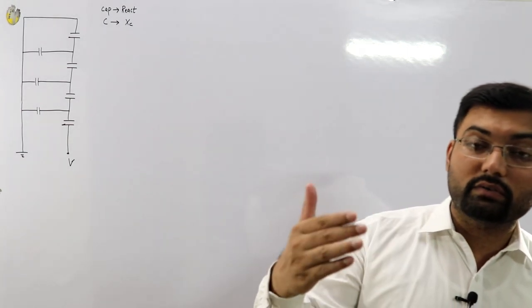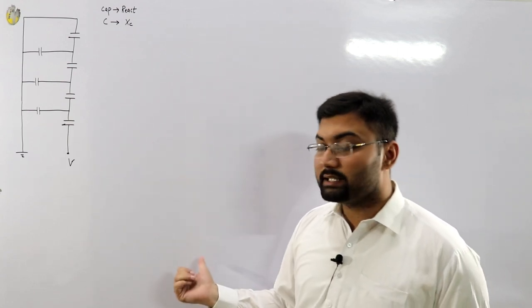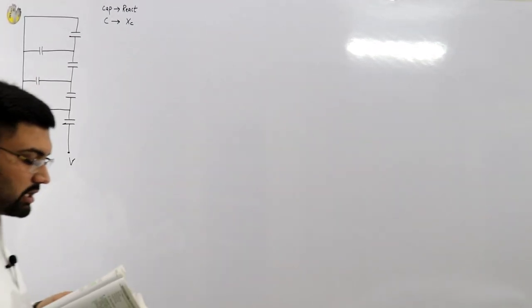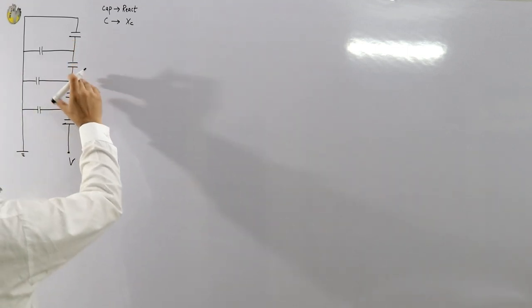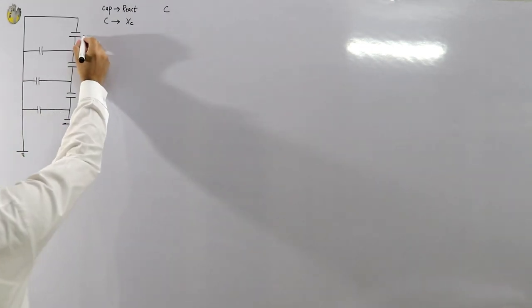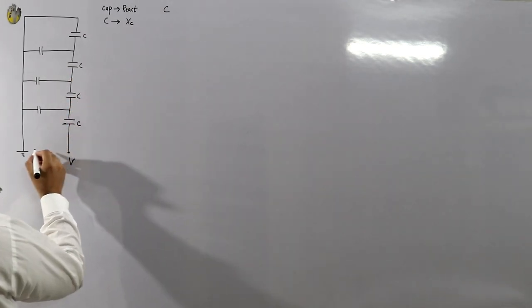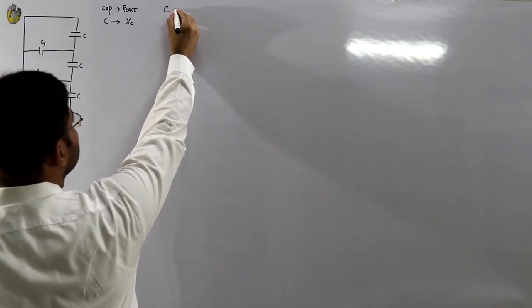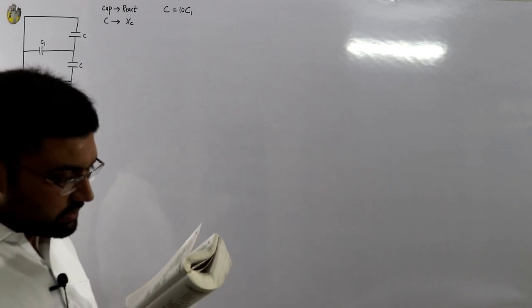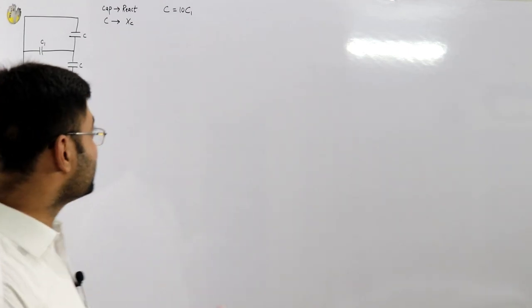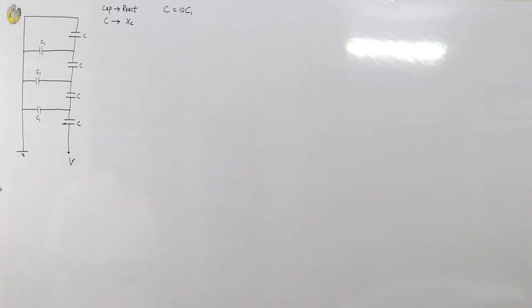When the number of discs exceeds three, this method is preferred, though it is equally applicable to two and three discs. Example 8.6 states: a string of four insulators has a self-capacitance equal to ten times the pin-to-earth capacitance. The self-capacitance is C and the shunt (pin-to-earth) capacitance is C1. We need to find the voltage distribution across the string as a percentage of total voltage, and then the string efficiency.